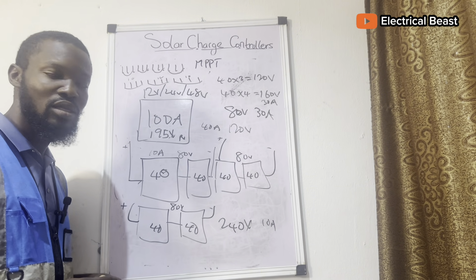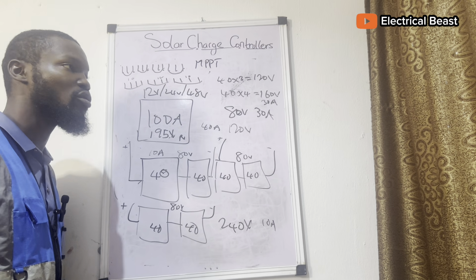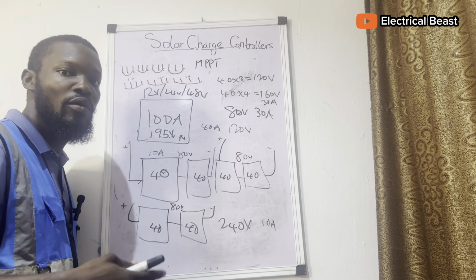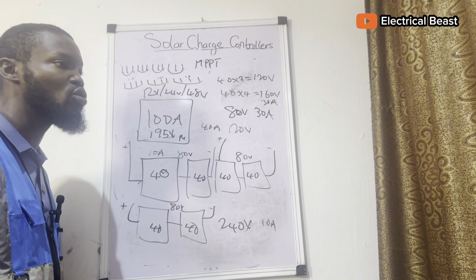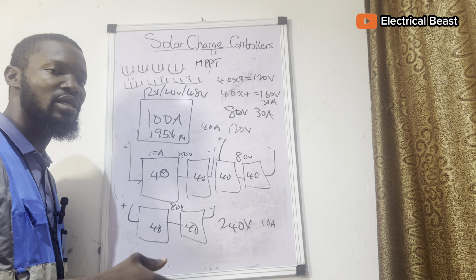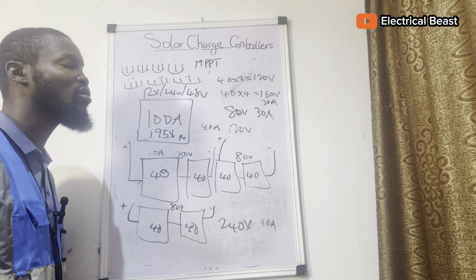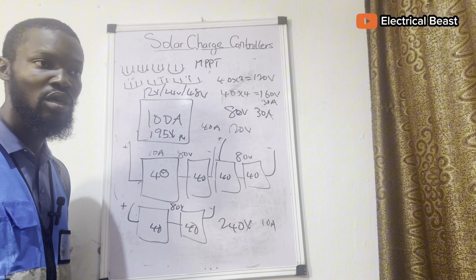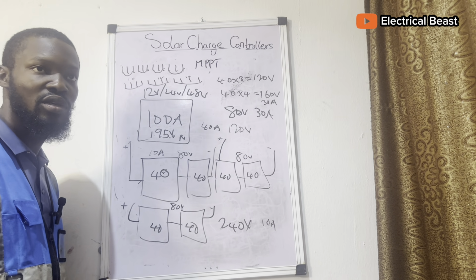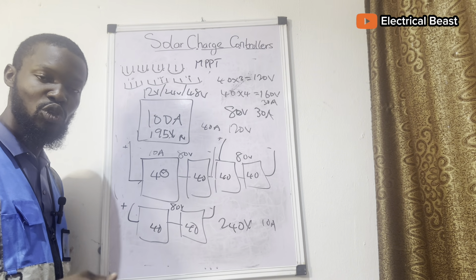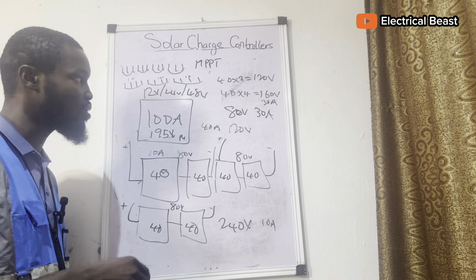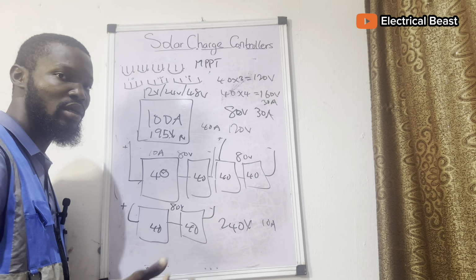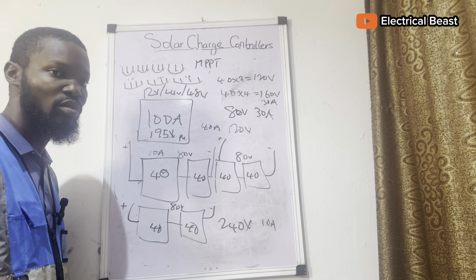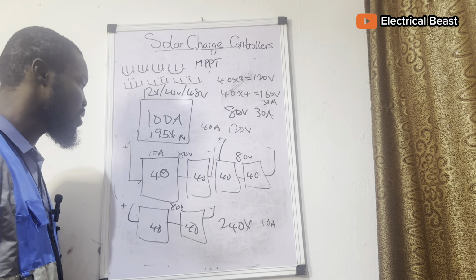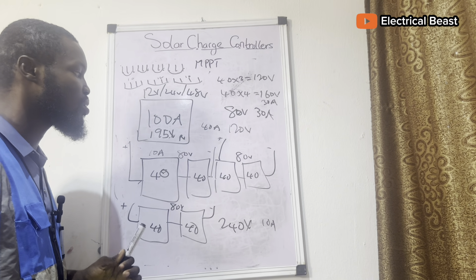In practical cases, you can have more than this. You can have up to 40 amps, 50 amps, 60 amps. So if the current is above 40, 50 amps, you need to use bigger size cables like 10 mm, 16 mm as the case may be. If you have up to 15 panels connected to a 120 amps controller, you need to make sure maybe you're connecting it 3 or 5. You need to use a cable size that is large enough to carry that current to your charge controller, and from your charge controller further to your batteries. Now that is that for MPPT charge controllers. Very important, very easy.